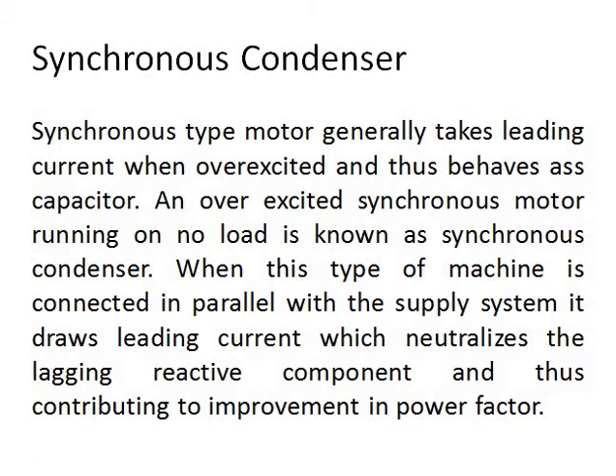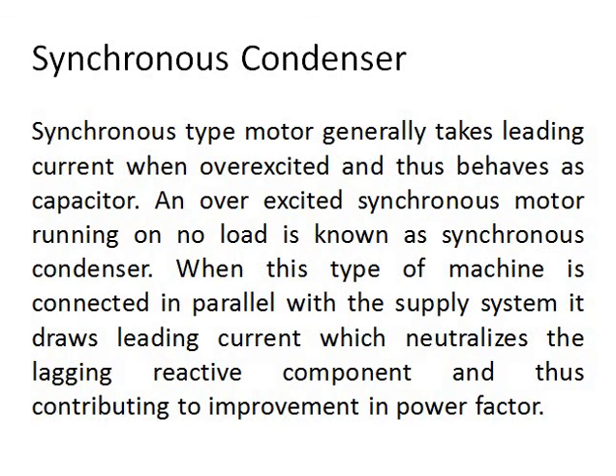We'll move to the next mitigation technique, that is making use of a synchronous condenser. Synchronous condensers are very large in size, and the noise they create poses a problem. Now, synchronous condensers are nothing but synchronous type machines, motors, which generally take leading current when overexcited and thus behave as capacitors.